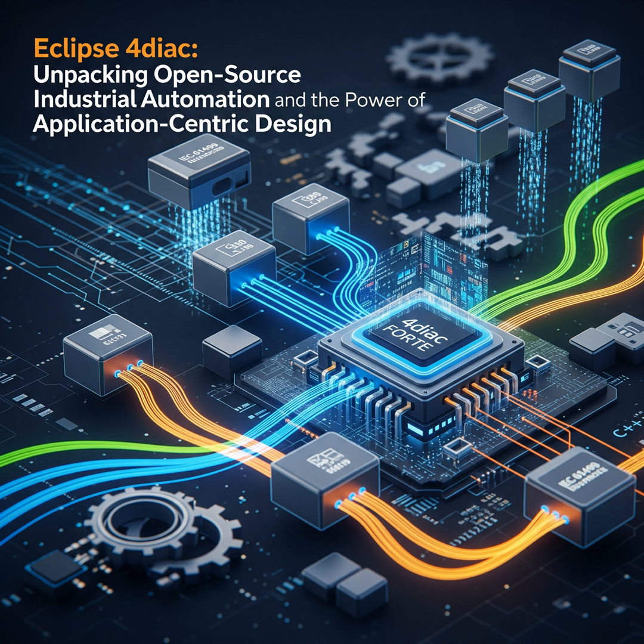Precisely. But its core philosophy, the really big idea, is application-centric design. This is kind of a mind shift. It means you think about and build the overall application first, what your system needs to do, often before you even know the exact hardware. You design this by interconnecting the desired function blocks, FB, in terms of a function block network, FBN. Hold on, function blocks, FBs, those are the digital Legos you mentioned. Yes, exactly. Think of them as little packages of industrial logic, reading a sensor, controlling a motor, a safety check, things like that. Okay, and the FBN, the network, is how you connect them visually.